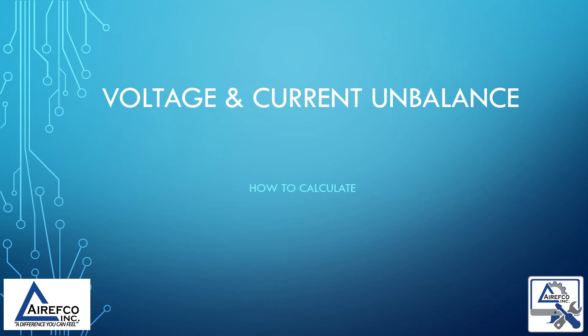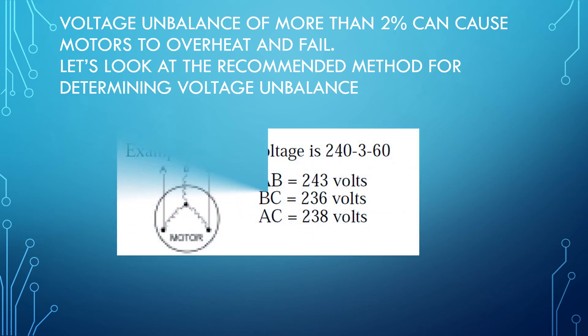Voltage and current unbalance — how to calculate it. Voltage unbalance of more than 2% can cause motors to overheat and fail. Let's look at the recommended method for determining voltage unbalance.